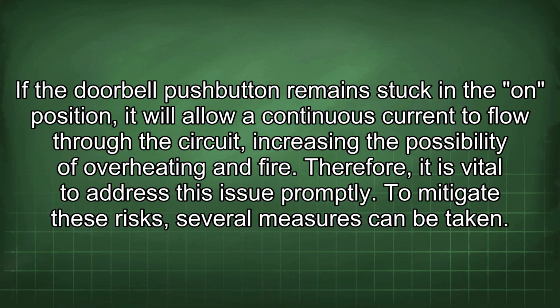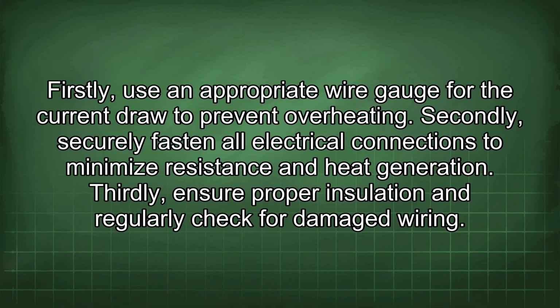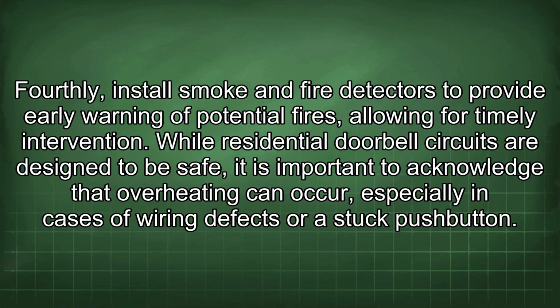To mitigate these risks, several measures can be taken. Firstly, use an appropriate wire gauge for the current draw to prevent overheating. Secondly, securely fasten all electrical connections to minimize resistance and heat generation. Thirdly, ensure proper insulation and regularly check for damaged wiring. Fourthly, install smoke and fire detectors to provide early warning of potential fires, allowing for timely intervention.